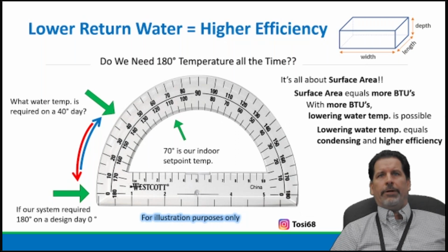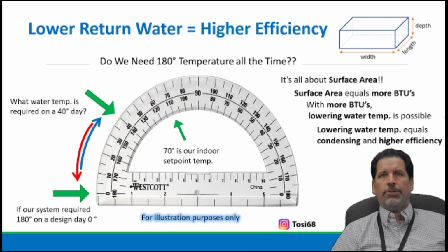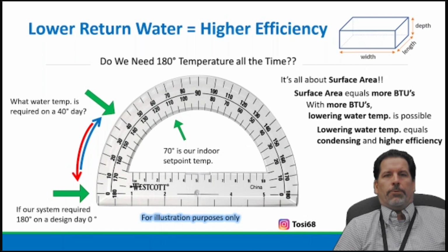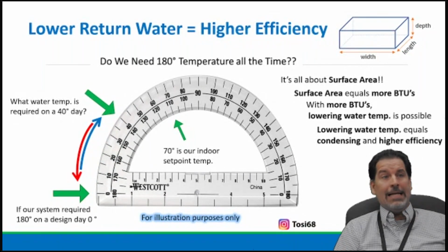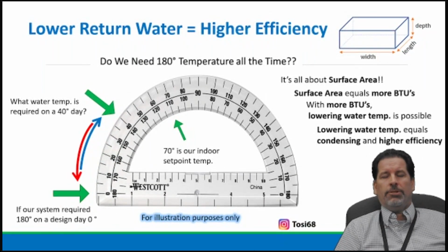So you can see the little note there, it's all about surface area. Surface area equals more BTUs. The more BTUs, the lower the water temperature can be, right? So that's key. Looking at the protractor here on the left side going up, what is the water temperature required for a 40-degree day? Not 180. The house doesn't lose the BTUs as it does on the coldest night. Warm goes to cool, it will find its way out of the house, the structure.